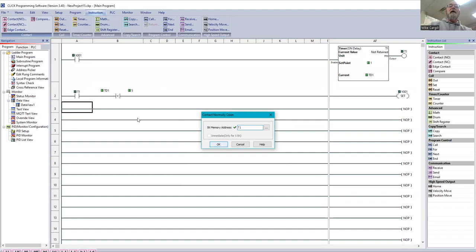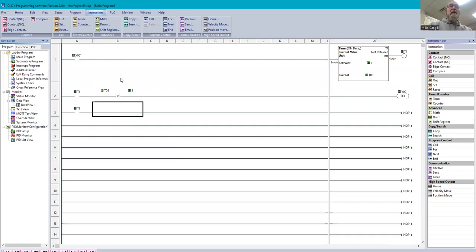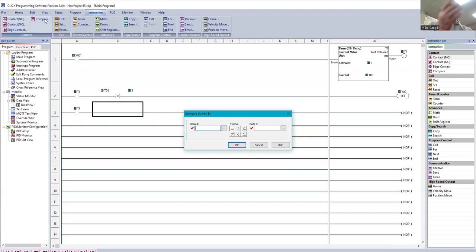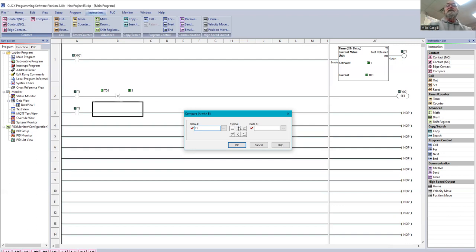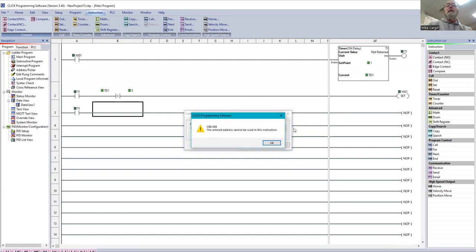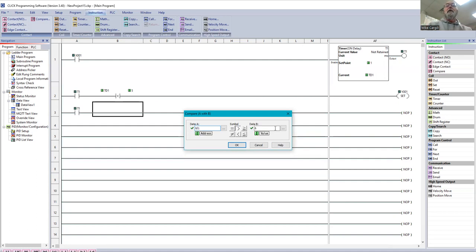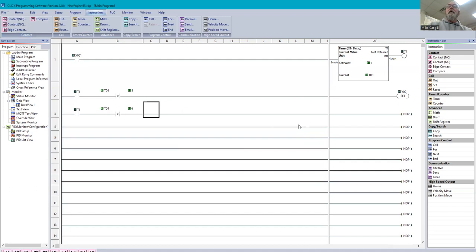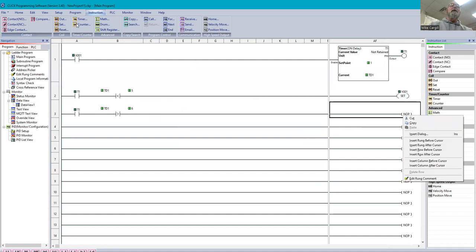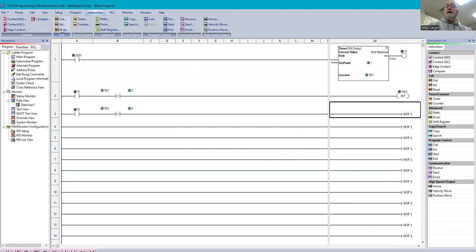Now we're going to come down here. We're going to do T1, an open contact. Now we're going to compare. And this time, if it's greater than five, let's say greater than six. TD1 is greater than six. That gives us a little cushion. We're going to have an output, and our output is going to be a reset. Reset means we're going to turn it off.